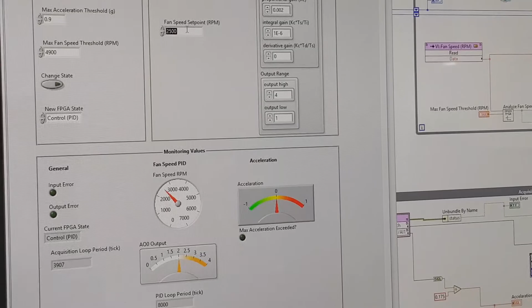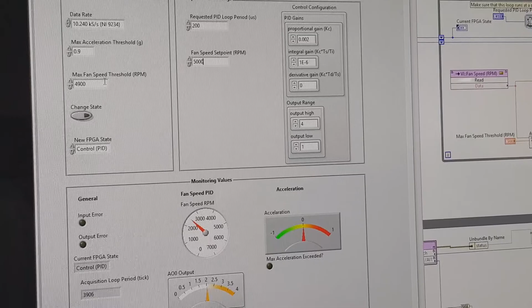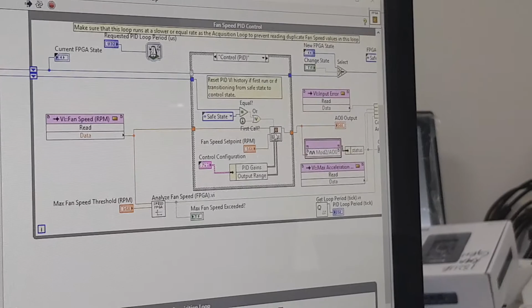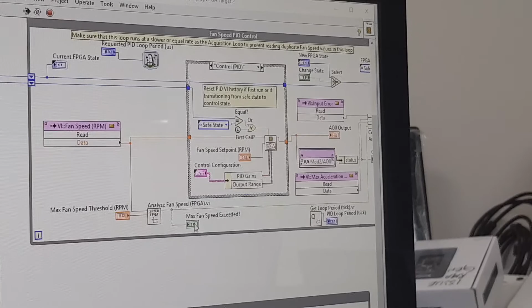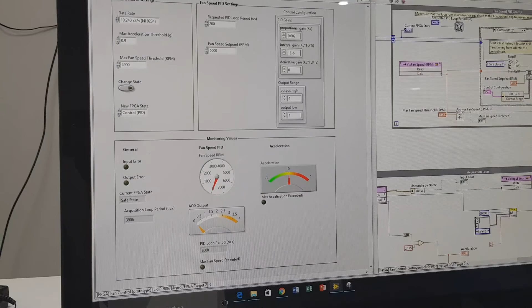Now I am making it 5000 RPM. Whenever I make it 5000 RPM, it will certainly cross the maximum fan speed threshold. If it crosses, the PID loop will alert it to go to the safe state. So it will jump to the safe state, because you have mentioned in this loop that if the maximum fan speed is exceeded, then go to the safe state. You see, it went into the safe state. So now the plant is off, because whenever it goes to the safe state, it will turn off the fan, meaning the plant will be off.